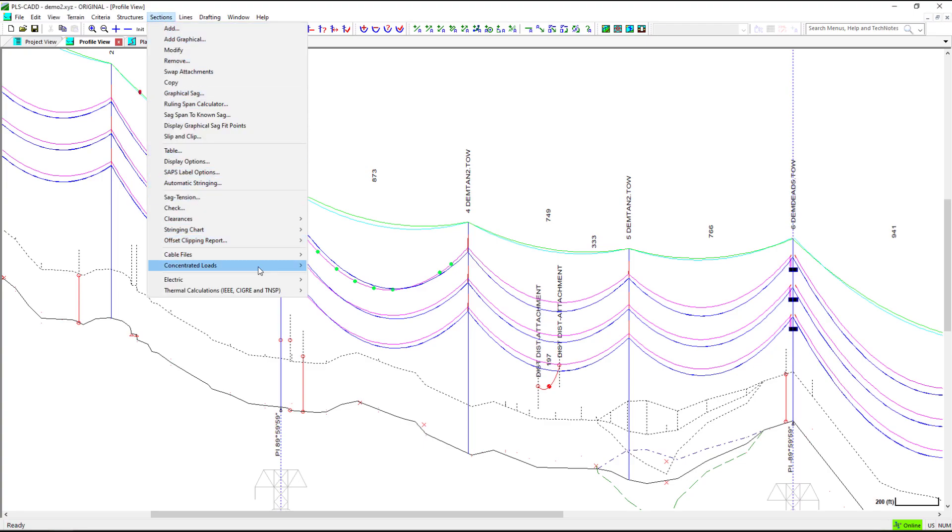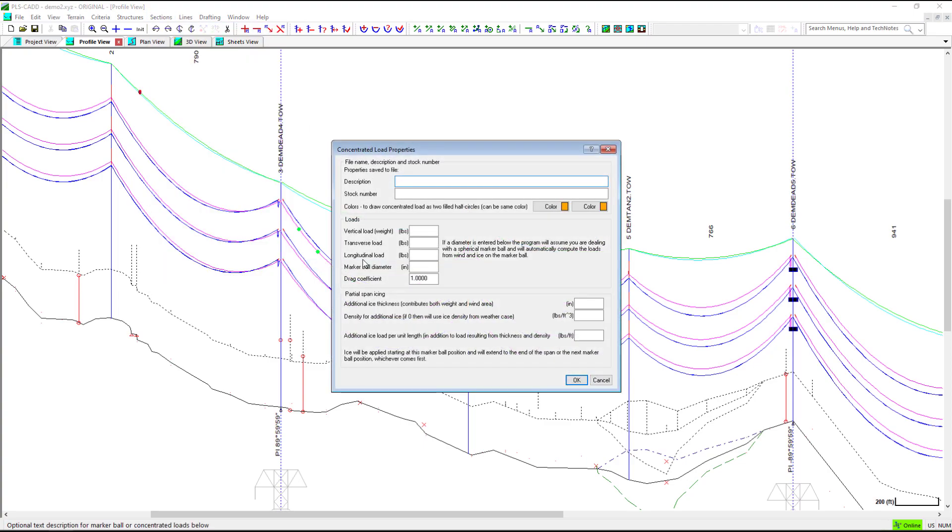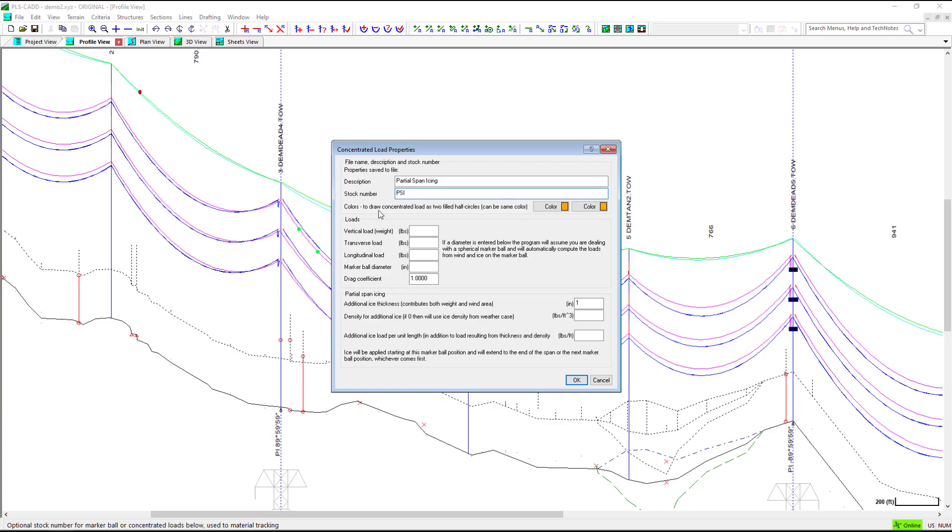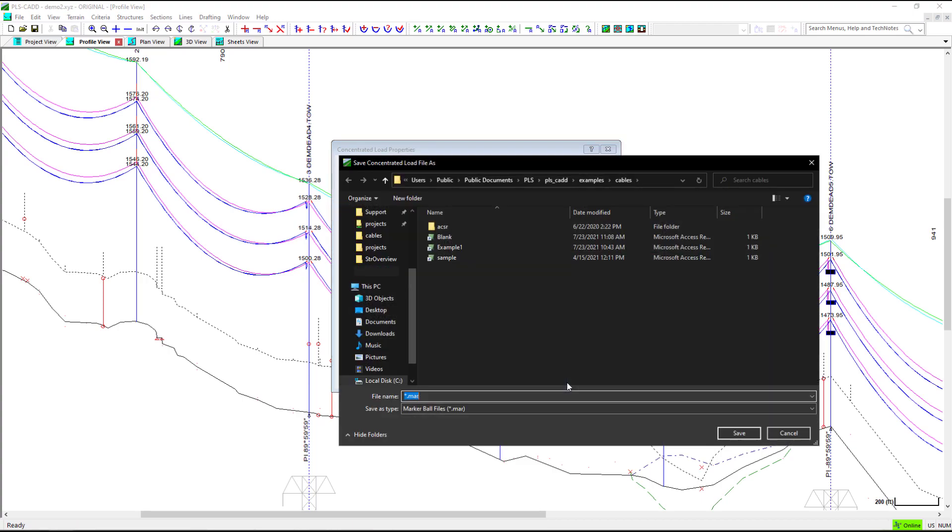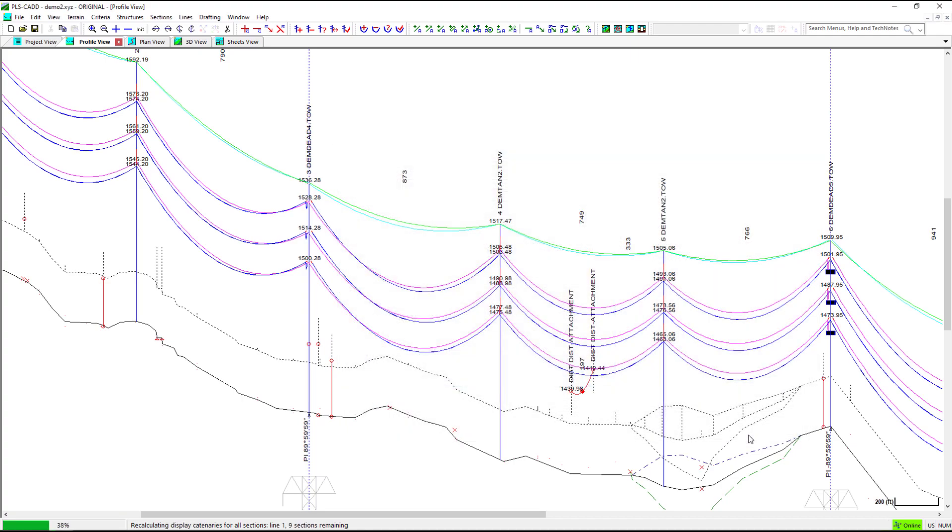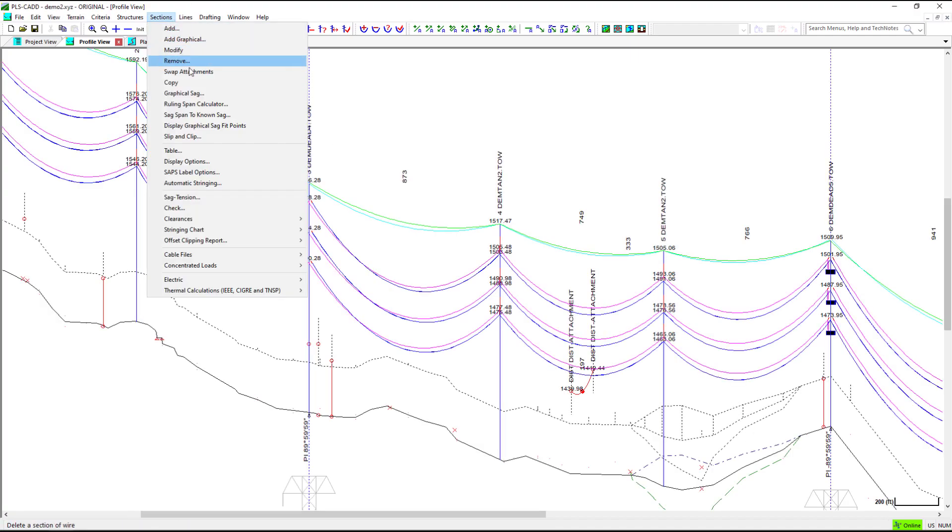Next, we will create a partial span icing concentrated load file. We will add an additional ice thickness of 1 inch. When we place the partial span icing concentrated load on the wire, the additional ice thickness begins at the location of placement and continues throughout the rest of the span.